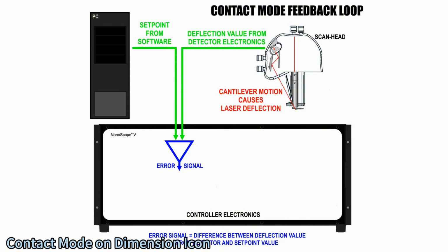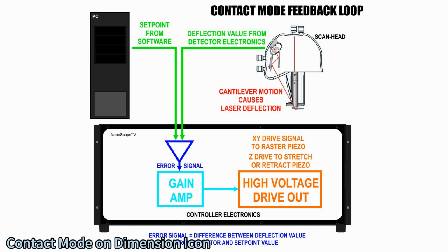The error signal is fed to a gain amplification circuit which influences the controller's response to the variation from the set point. The amplified values are then fed to the high voltage control circuitry to send the required voltage values to the scanner that will force the piezo to retract or extend to maintain the set point deflection value.